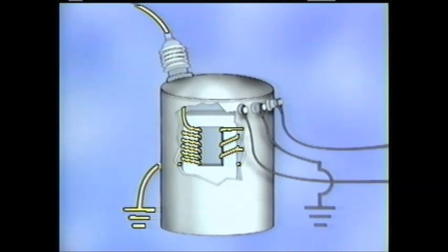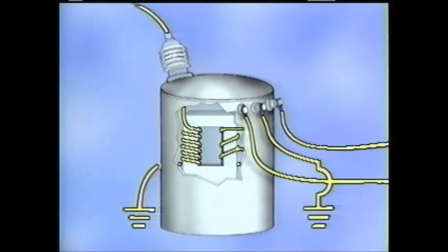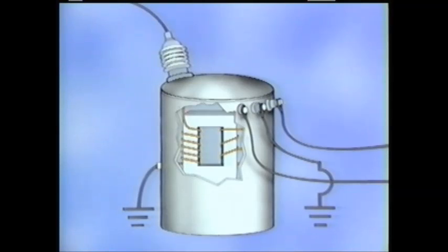The secondary, or utilization, voltage induced in the secondary winding is tapped off the transformer through leads that pass through the secondary bushings on the side of the housing. In this example, the lead passing through the middle bushing on the secondary side is grounded. The leads on either side are hot. The secondary leads are usually connected to wires that form a secondary bus, which supplies consumers with electricity through service drops.